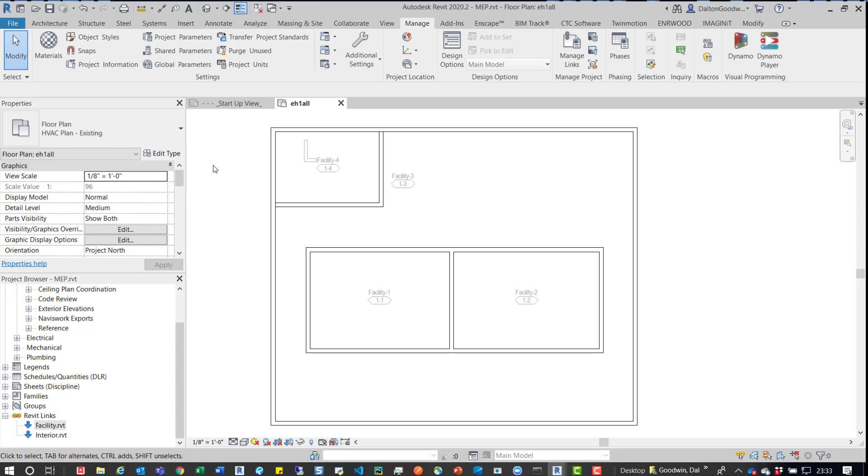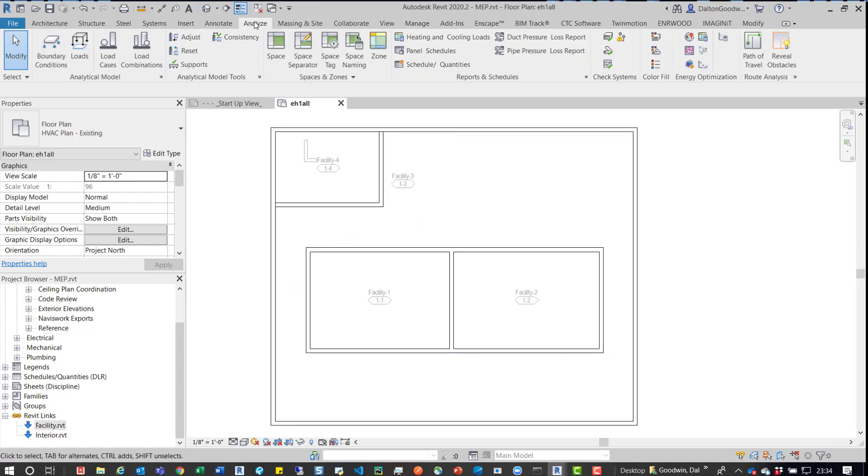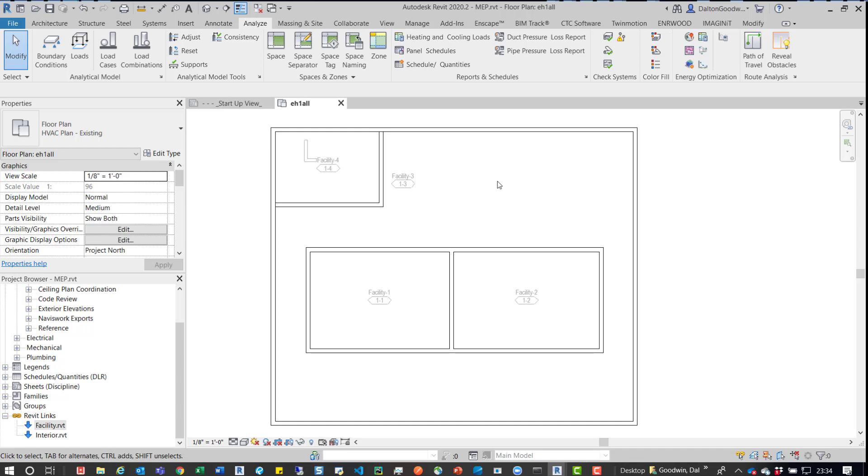So at any point, we could also go into that facility model and actually delete that space entirely, which would then allow us to simply load it in. Even if it was the first, we would just reload the link. We wouldn't remove the link. We would just reload it after we've deleted that space. Run the space naming from the Analyze tab and then we're good to go. It'll name it correctly even if it takes the facilities as a priority.